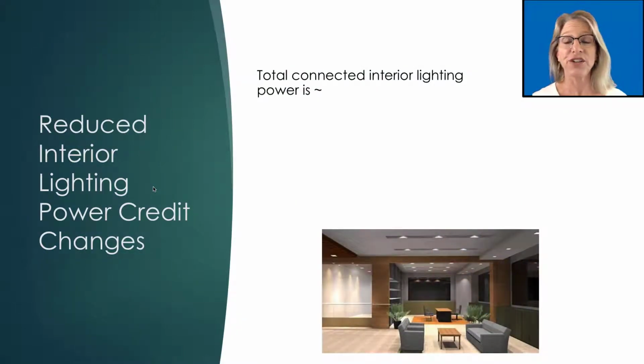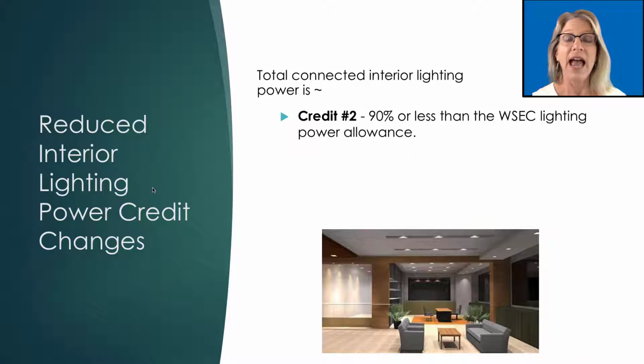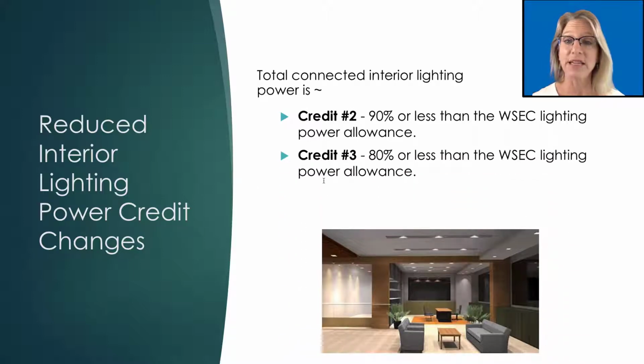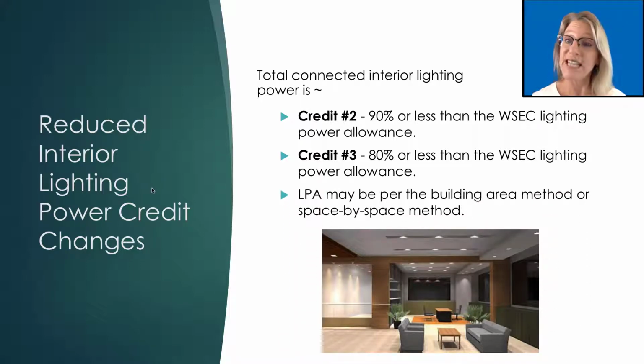So we'll cover all of the additional efficiency credit changes in our next episode. However, here's a sneak peek to explain the changes to the efficiency credits for interior lighting. Note that in the 2018 WSEC, these are referred to as credits and not options. So in a nutshell, this one credit package has been divided into two in the 2018 WSEC, with one credit set aside for projects where the LPD is 90% or less than the lighting power allowance, and the other is for projects where the LPD is 80% or less than the LPA. Stated differently, there are credits available for projects where the lighting serving a building or space is 10% or 20% lower than the code maximum LPA. These LPA credits may be determined using the building area method or the space-by-space method.